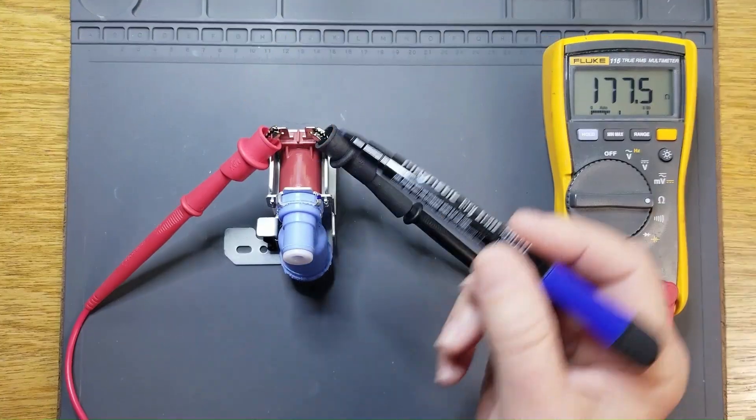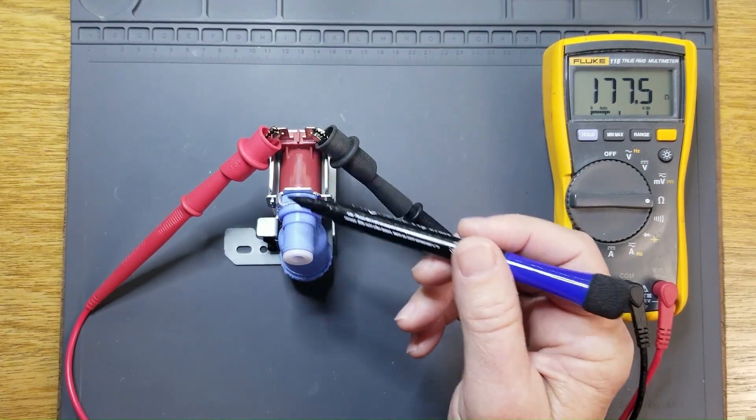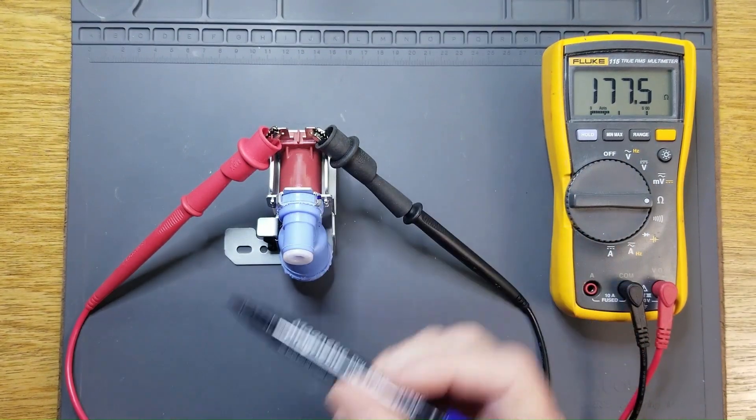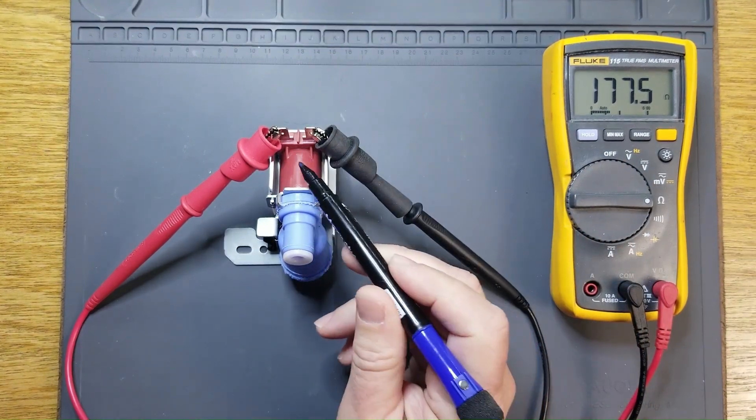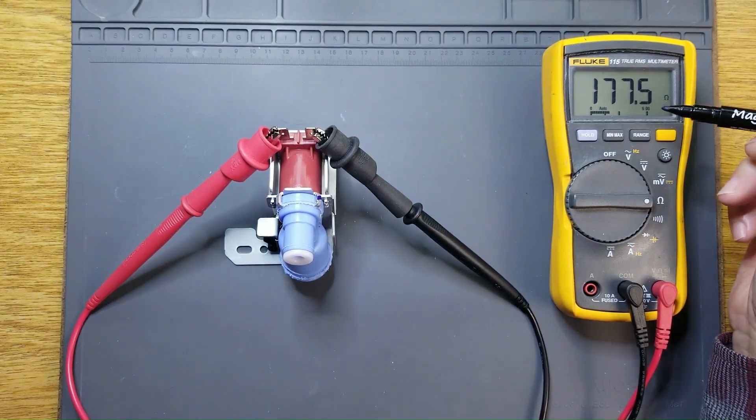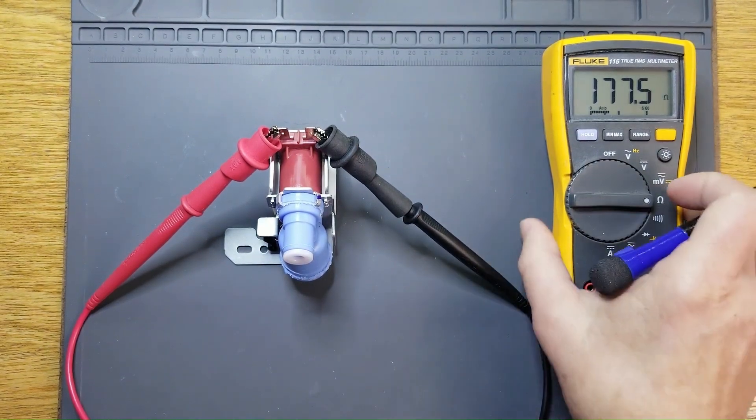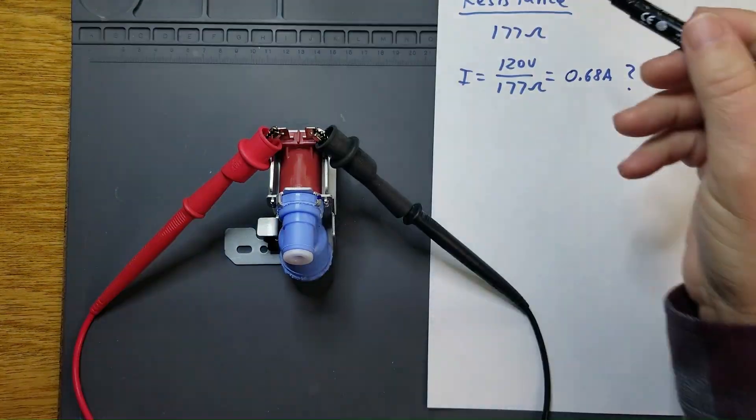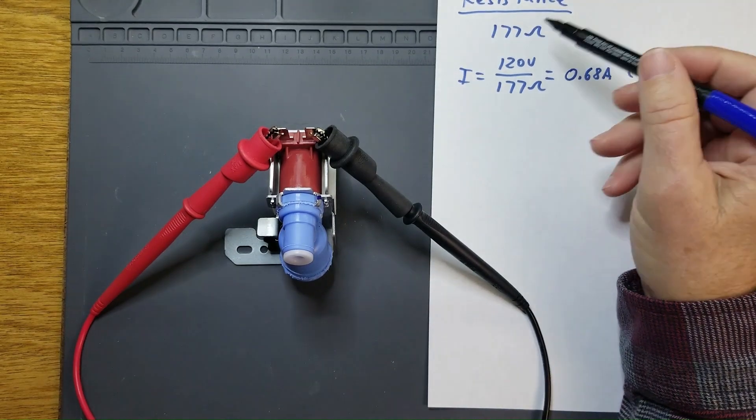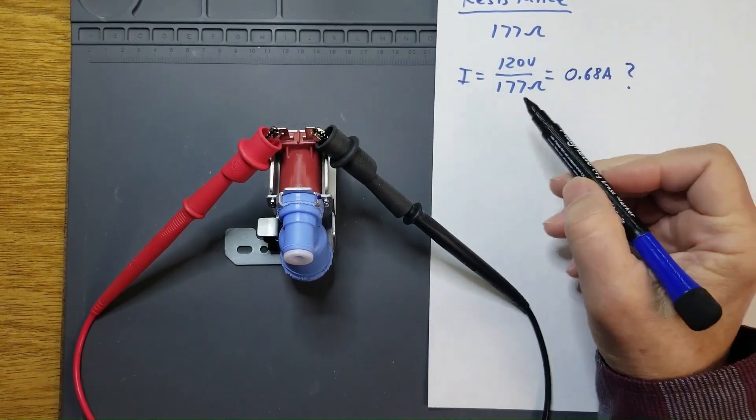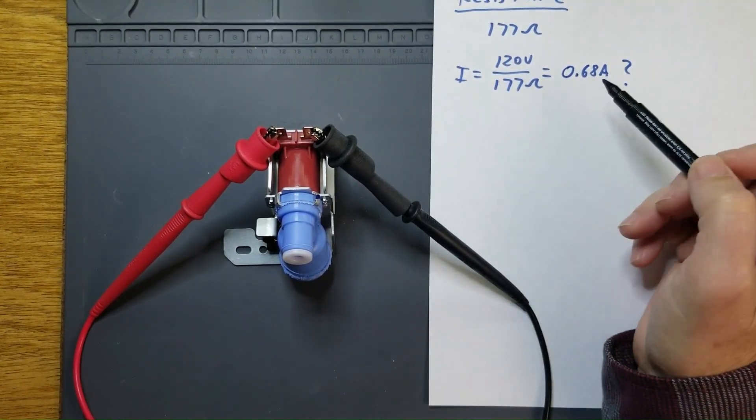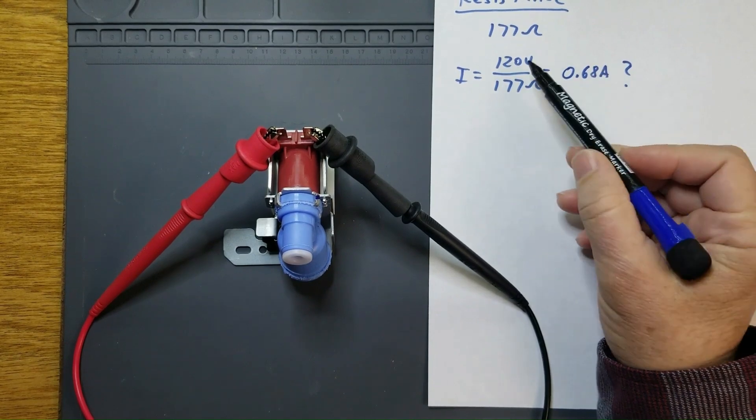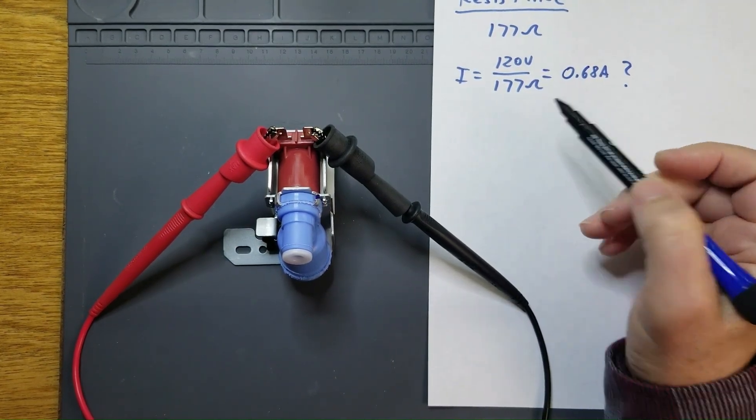The same concept applies to this refrigerator inlet valve solenoid. The measured resistance of this solenoid is 177 ohms. So that would imply, if we were to rely solely on that resistance reading, that the current draw of this solenoid would be 120 volts divided by 177 ohms, or 0.68 amps.